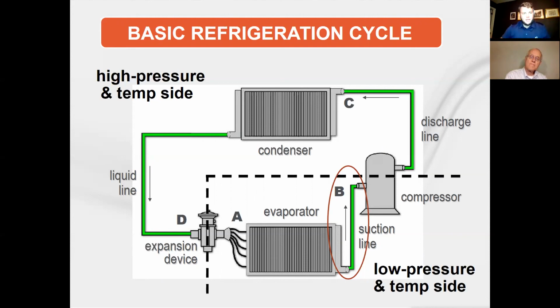Once you try to do that in a split system where you leave all of the in-between piping, you need 3 pipes at that point up to the field, and there's a lot more risk of compressor burnouts and oil management problems. So even when it is offered and carefully designed with the manufacturer you're working with, a lot of times the length limitations are cut in half. If you might have been allowed 100 feet before total separation, now they'll say maybe max 50 feet or something. And even then they want to be in charge of strict pipe sizing guidelines and all that.